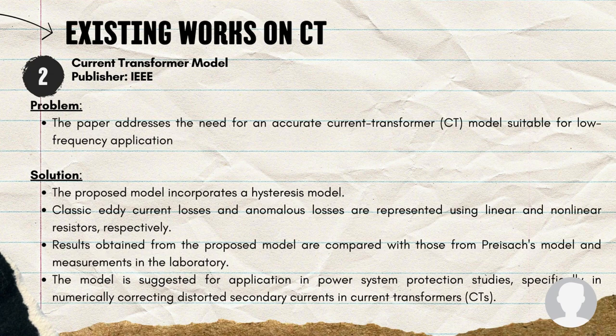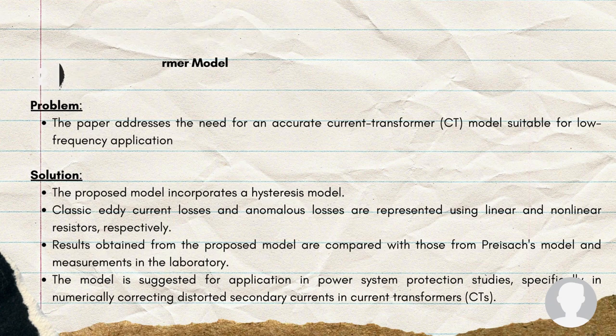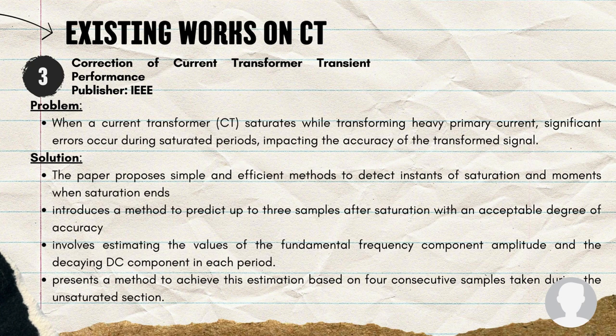For the next research, the problem is the need for an accurate CT model suitable for low-frequency applications. The proposed model incorporates a hysteresis model where classic eddy current losses and anomalous losses are represented using linear and nonlinear resistors respectively. The results from the proposed model are compared with Preisach's model and laboratory measurements. For the last research, the problem is that when a current transformer saturates while transforming heavy primary current, significant errors occur during saturated periods, impacting accuracy. The solution is a simple and efficient method to detect instants of saturation and when saturation ends, predicting up to three samples after saturation with acceptable accuracy, and estimating the fundamental frequency component amplitude and decaying DC component in each period.